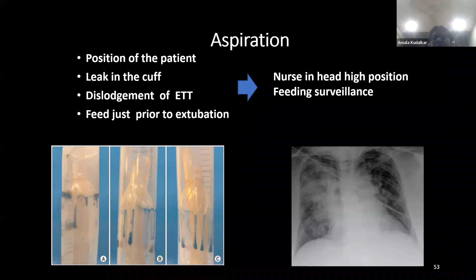Many a time you have used a cuffed endotracheal tube, but usually the secretions accumulate above the cuff. And that's why you can use an endotracheal tube with a subglottic secretion drainage port. This is the cuff and there is a port here. There is a small hole in the shaft of the endotracheal tube just above the cuff. A channel runs inside the wall so that it can be sucked.